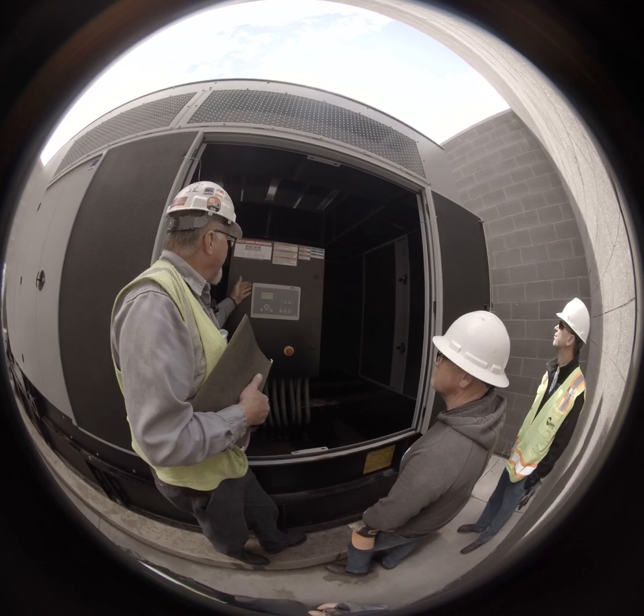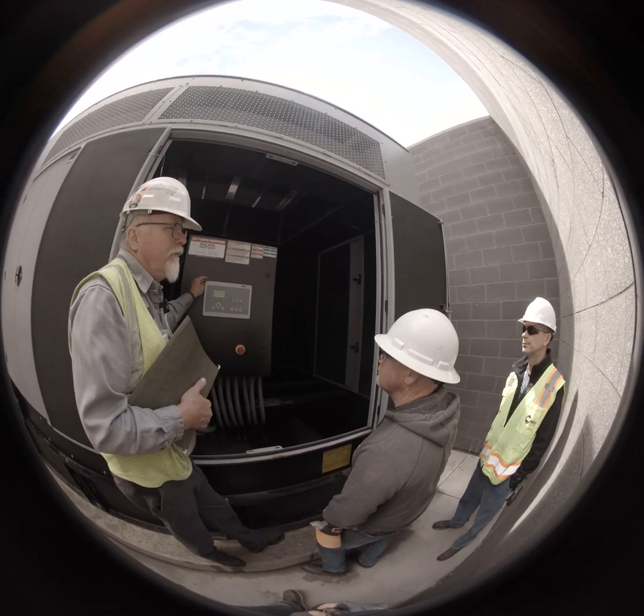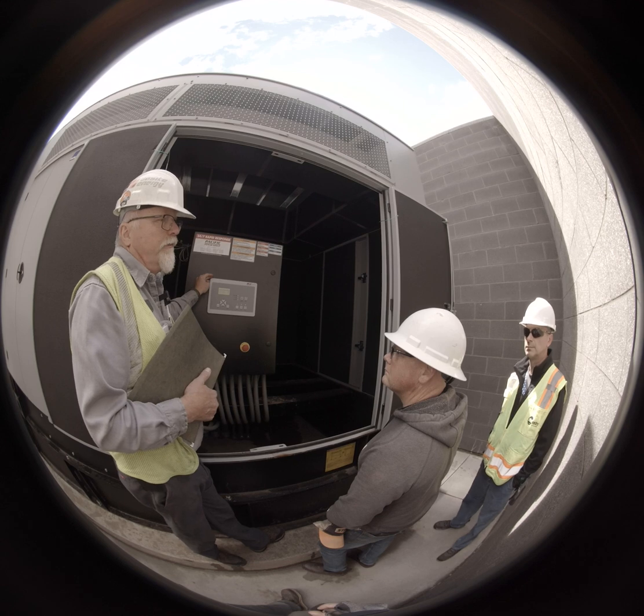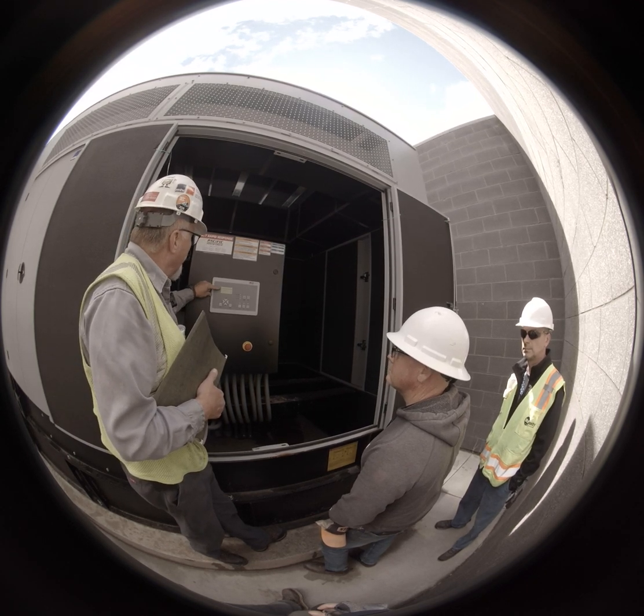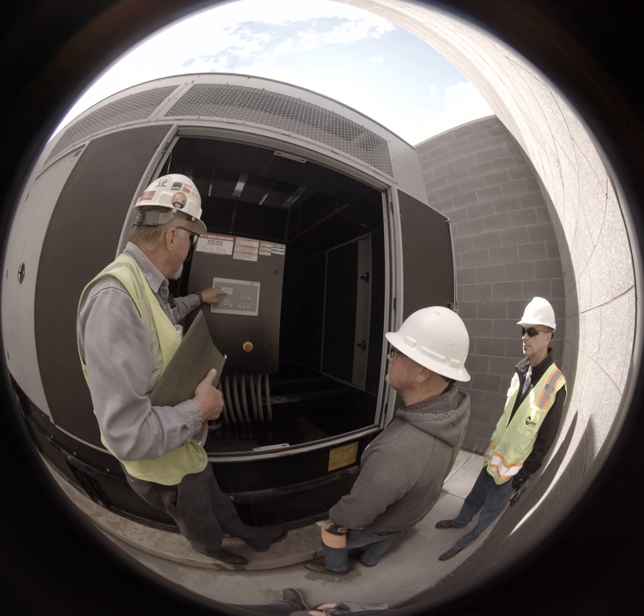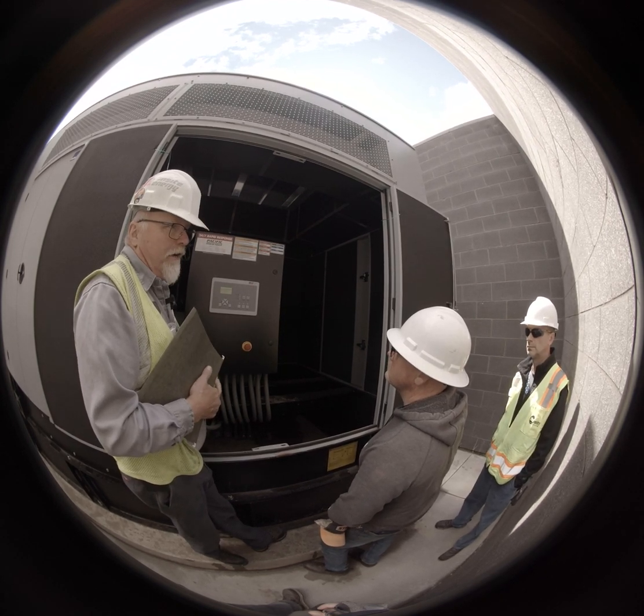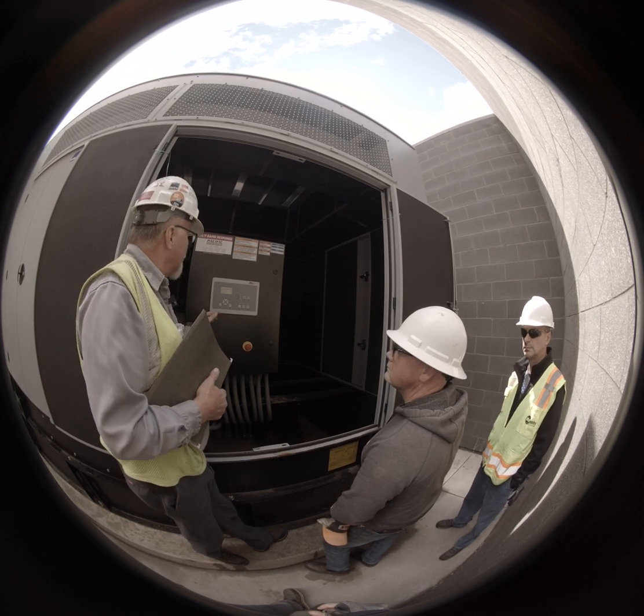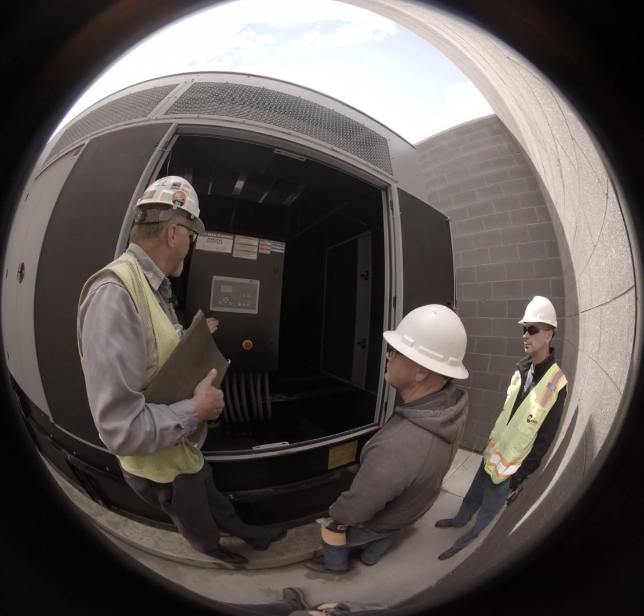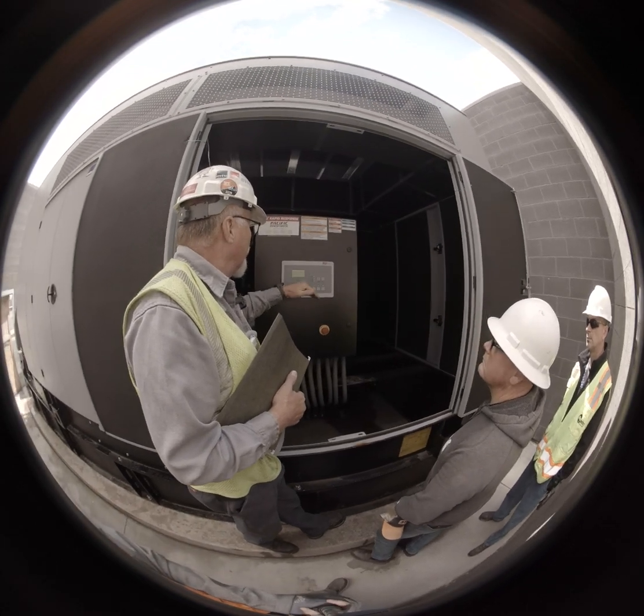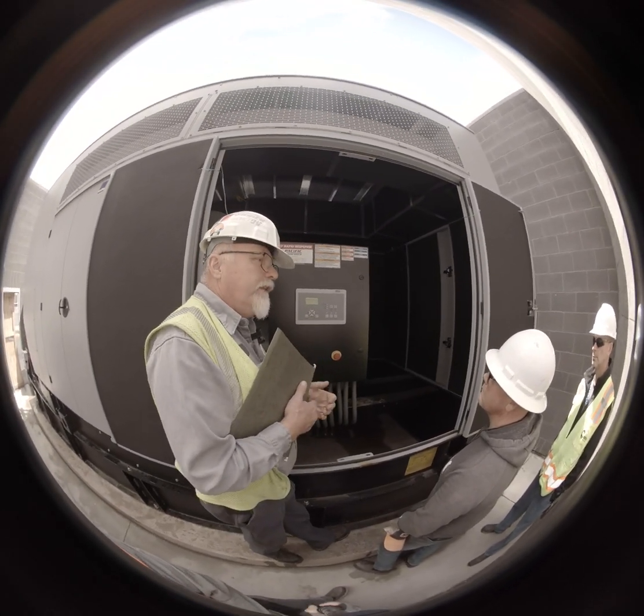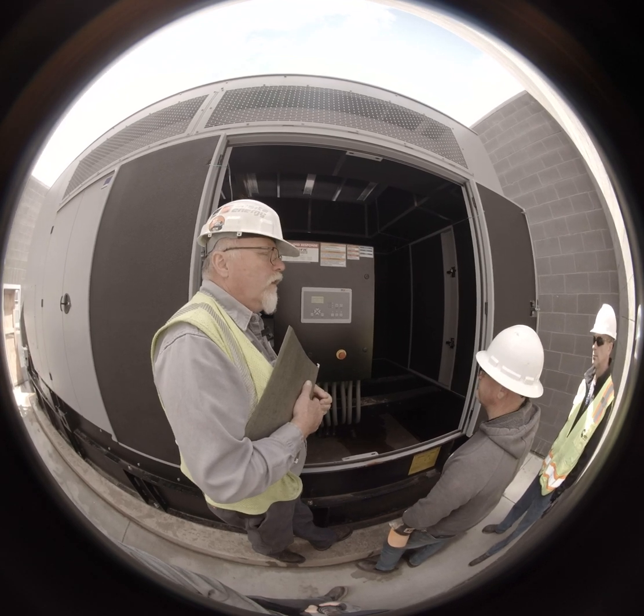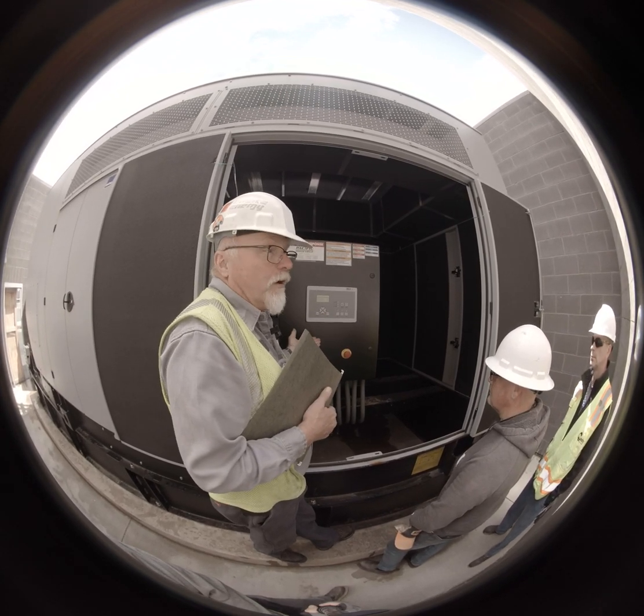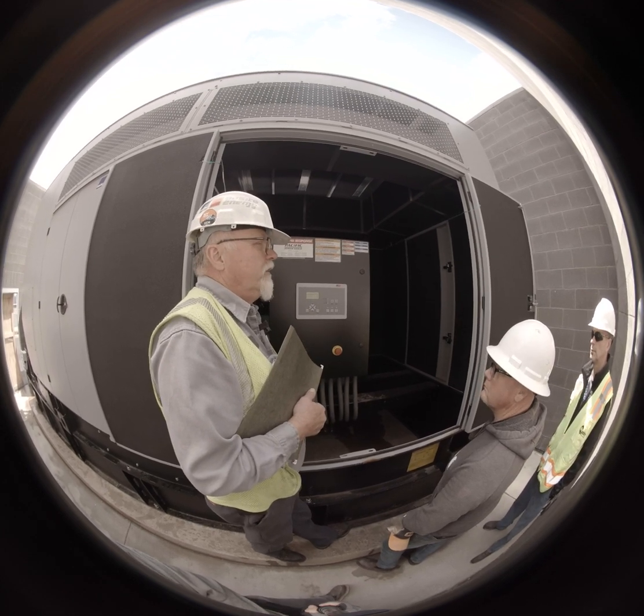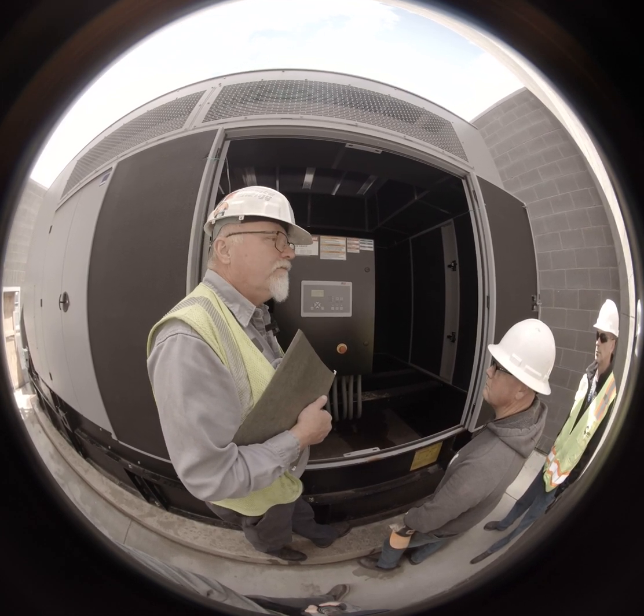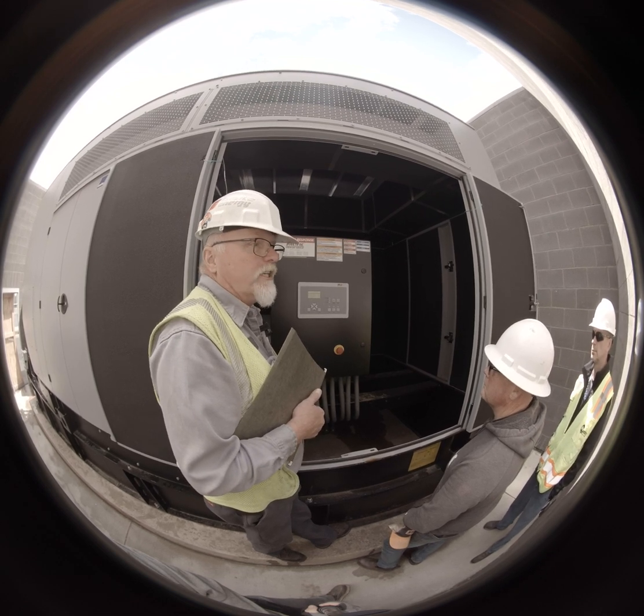So this genset is set up to operate from a contact closure from the automatic transfer switch. So this first one is automatic transfer switch. That's the input. And it says that input is off. If the transfer switch calls for this to run, then you'll see that will say yes, meaning that it's a closed contact. Once that closes, the gen should start. So it's a good way to troubleshoot. I'll go in here and they say, well, the gen, it's calling for it, but won't start. And I'll walk out here like, yeah, no, it's not. We'll usually find a wire connection or something of that nature.